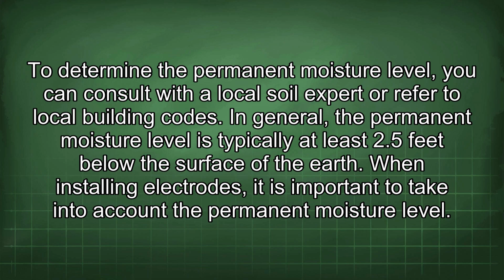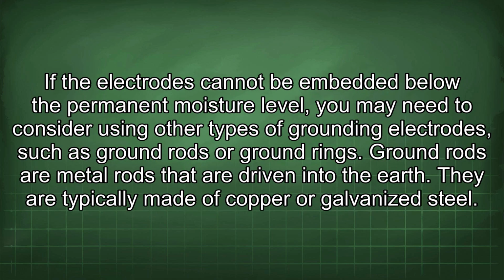To determine the permanent moisture level, you can consult with a local soil expert or refer to local building codes. In general, the permanent moisture level is typically at least 2.5 feet below the surface of the earth. When installing electrodes, it is important to take into account the permanent moisture level. If the electrodes cannot be embedded below the permanent moisture level, you may need to consider using other types of grounding electrodes such as ground rods or ground rings.